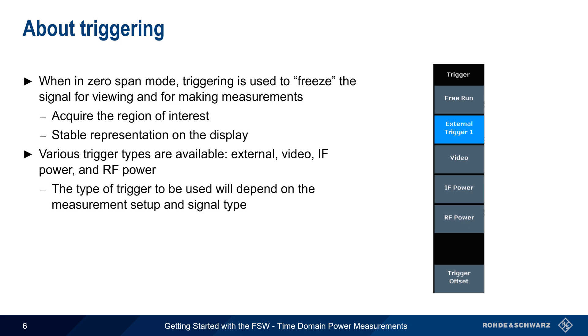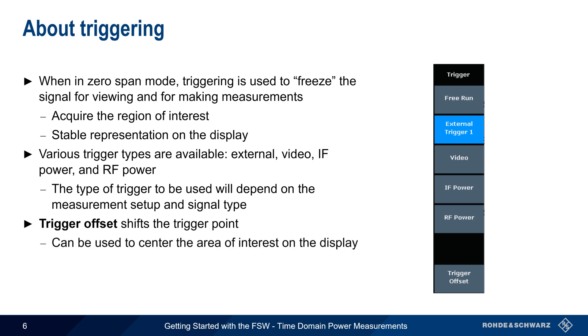The trigger type used will depend on the measurement setup and the signal type, and in many cases acceptable results can be obtained using any one of these trigger types. Another trigger-related parameter is trigger offset, which can be used to shift the position of the trigger point. This can be used to center the area of interest on the display — for example, moving a pulse to the center of the screen rather than having it appear on the edge.